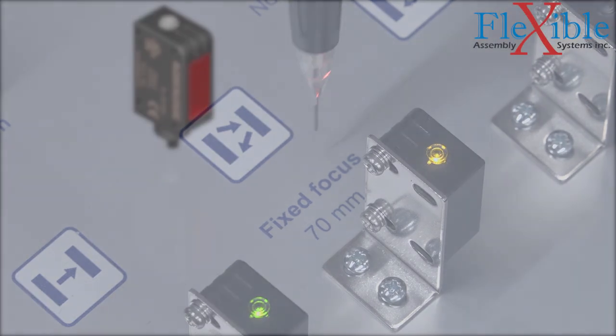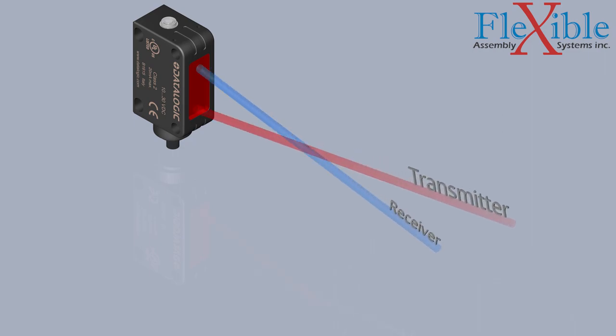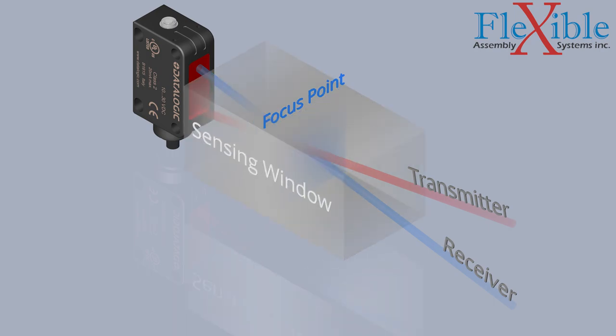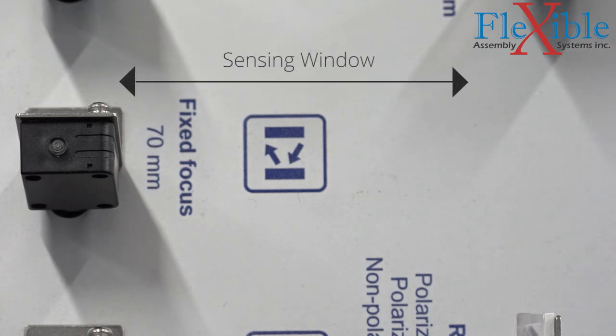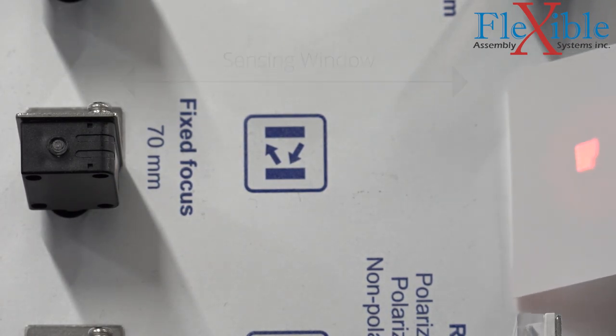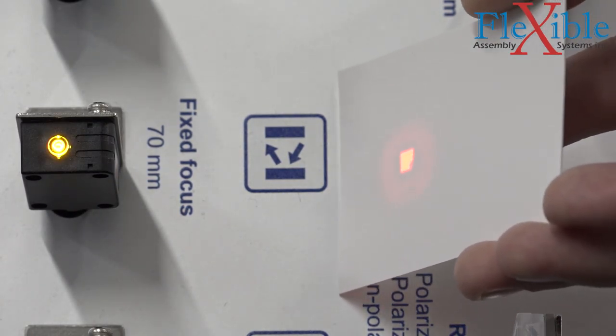In a fixed focus sensor, the transmitter lens and receiver lens are both focused to the same point in space. This point, plus or minus a known distance, is now our sensing window. The sensor will only be able to see targets if they pass through this fixed detection range. Objects outside of it will be ignored.